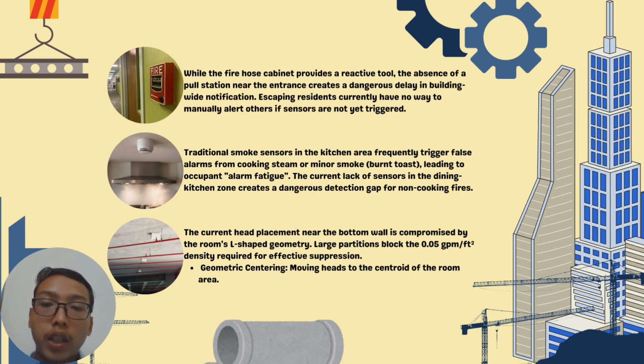After that, lastly, the current head placement near the bottom wall is compromised by the room's L-shaped geometry. The large partition blocks the 0.05 gallons per minute per square foot density required for effective suppression. For the improvement, geometric centering, moving heads to the centroid of the room area.